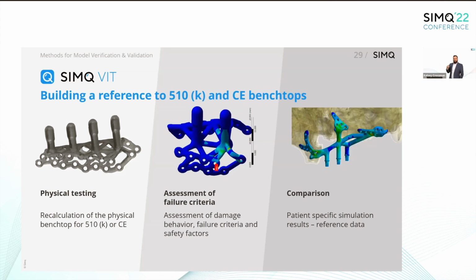To show you how we build the reference to the material limit, the basic idea behind it is we are taking physical tests from 510K or CE and recalculate these physical benchtop tests. And with the known damage criteria, damage behavior, we can assess failure criteria. So we can say what is the damage behavior, how much strains and stresses are allowed under cyclic load, etc., and come up with these failure criteria and put on some safety factors. It's really safe for the patient.